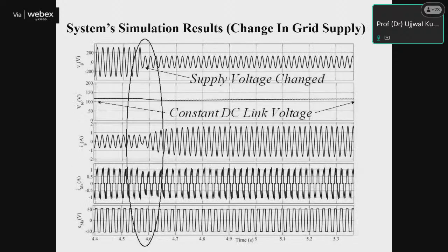This is the system performance under dynamic operating conditions — we are increasing the load, and suddenly we have changed the supply voltage, reducing it. Momentarily the DC bus voltage reduces, but it immediately regains the same DC link voltage, and speed is also maintained at the same value. Grid current increases automatically in order to supply the same power to the motor drive when supply voltage reduces.